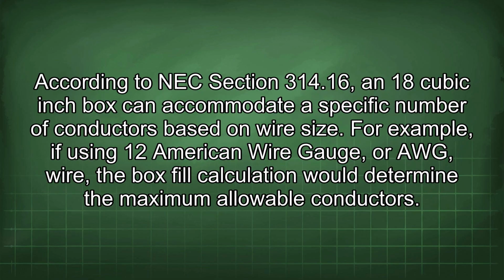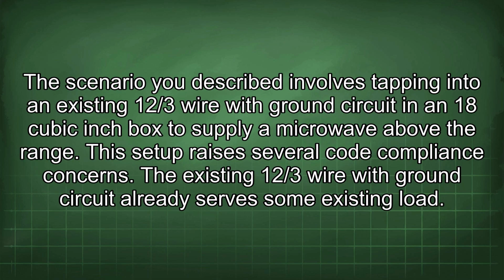According to NEC section 314.16, an 18 cubic inch box can accommodate a specific number of conductors based on wire size. For example, if using 12 American Wire Gauge, or AWG, wire, the box fill calculation would determine the maximum allowable conductors. The scenario you described involves tapping into an existing 12/3 wire with ground circuit in an 18 cubic inch box to supply a microwave above the range. This setup raises several code compliance concerns.